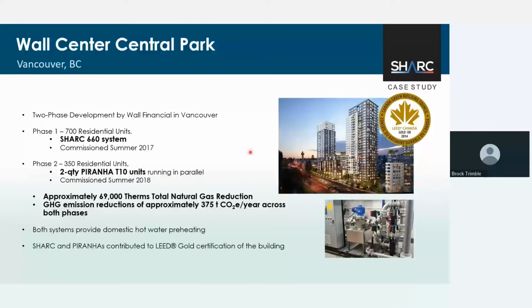Phase one has one of our SHARC 660 units that you can see down here, while phase two has two of our Piranha T10 units running in parallel. Both of these systems together result in roughly 69,000 therms of natural gas reduced in comparison to their baseline natural gas boilers. And this equates to roughly 375 tons of CO2e per year reduced across both phases. So as we start to scale up, you can really quickly see a massive impact as you're seeing more and more energy recovery, electrified output, and natural gas or fossil fuel offsets.